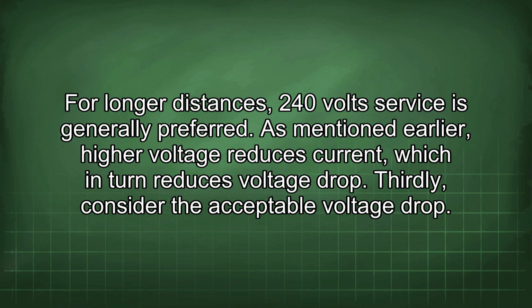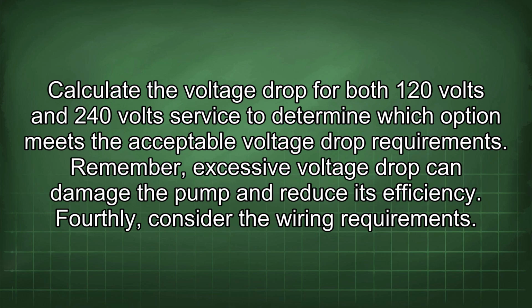As mentioned earlier, higher voltage reduces current, which in turn reduces voltage drop. Thirdly, consider the acceptable voltage drop. Calculate the voltage drop for both 120 volt and 240 volt service to determine which option meets the acceptable voltage drop requirements. Remember, excessive voltage drop can damage the pump and reduce its efficiency.